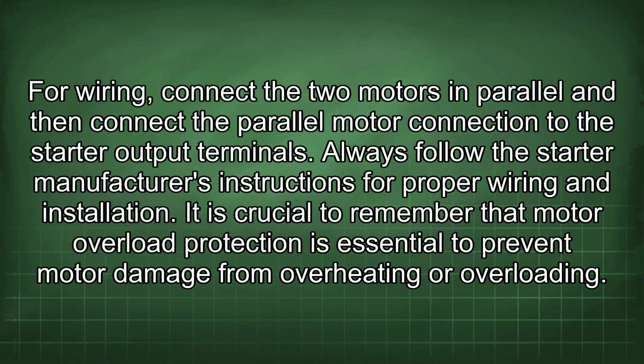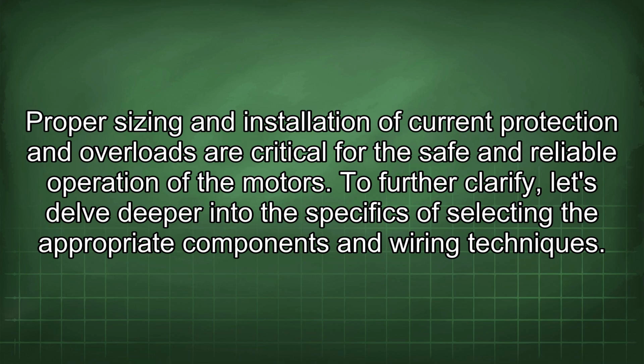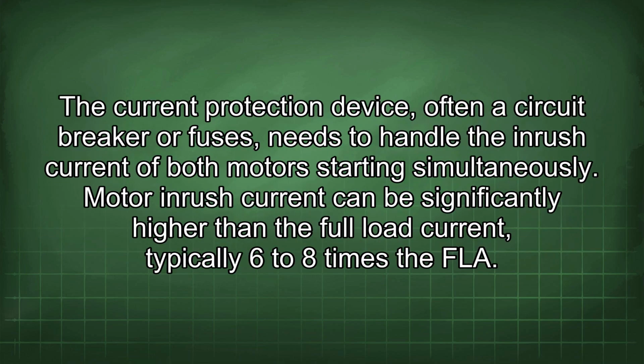It is crucial to remember that motor overload protection is essential to prevent motor damage from overheating or overloading. Proper sizing and installation of current protection and overloads are critical for the safe and reliable operation of the motors. To further clarify, let's delve deeper into the specifics of selecting the appropriate components and wiring techniques.